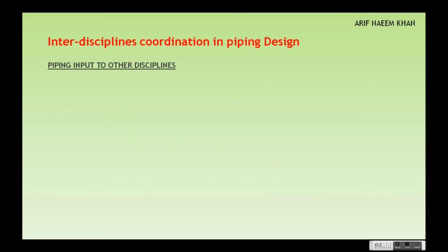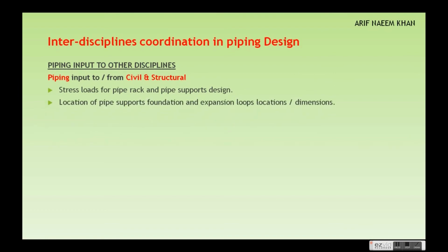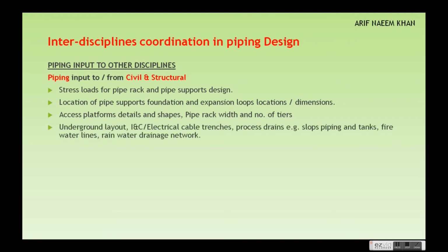Piping input to other disciplines, civil and structure: stress analysis loads for the pipe rack and pipe support will be designed based on the stress analysis input to civil and structure. The location of the pipe support foundation, and the expansion loop location and dimensions, need to be communicated properly to the civil and structural department. Access platforms, their details and shape, the pipe rack width and the number of tiers of the pipe rack also need to be properly communicated to the civil and structural department.